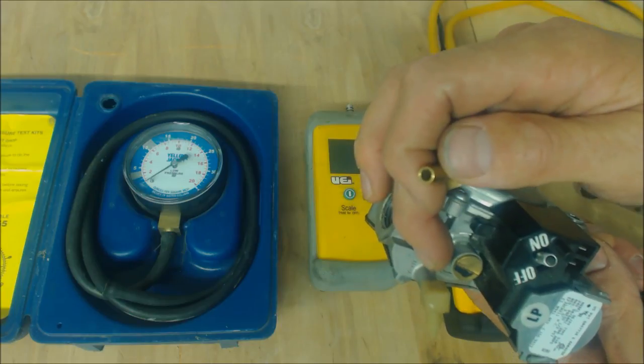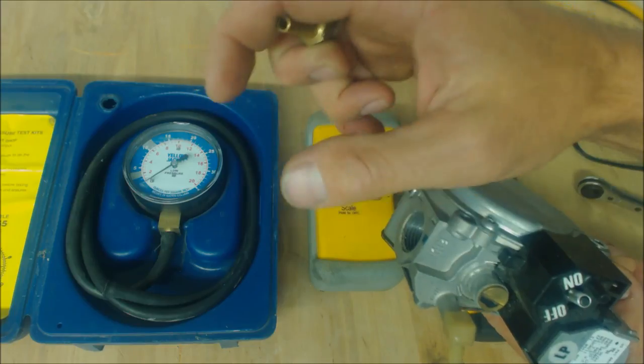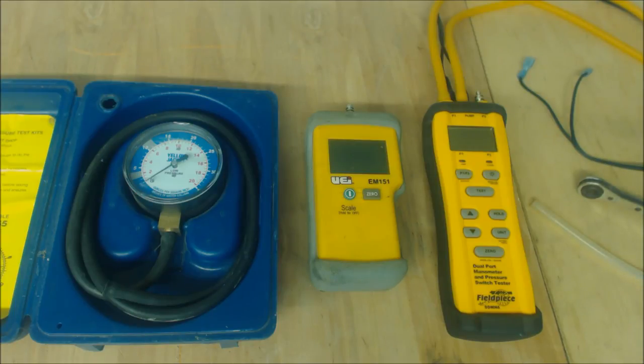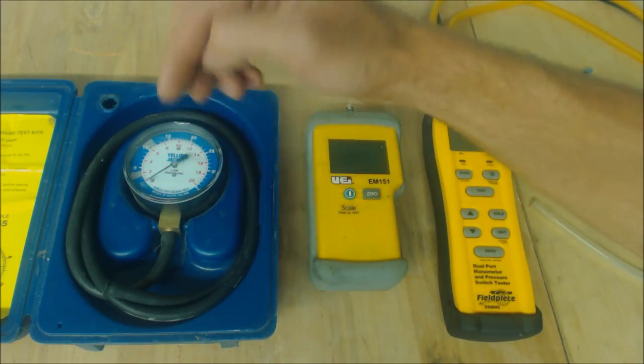If you see two brass screws, that means it's a two-speed gas valve. If you saw two brass screws here and possibly another brass screw over next to this, that would mean it's a three-stage gas valve.